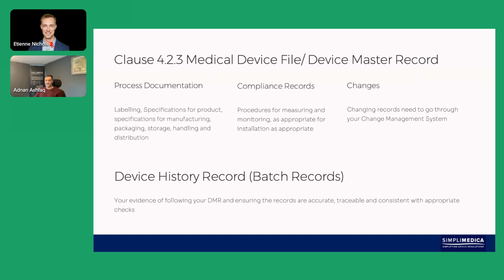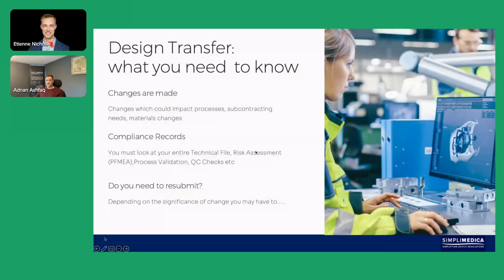Now, the device history record, or the batch records, is your evidence of following your DMR and ensuring the records are accurate, traceable, and consistent with appropriate checks. ISO 13485 does not specifically call out a device history record like clause 4.2.3 does for the medical device file, but in production and service provision in clause 7.5, it requires records for production. And if you think of it this way, you might also have your device history record as part of your medical device file. Either way, you've got to ensure those records are there.